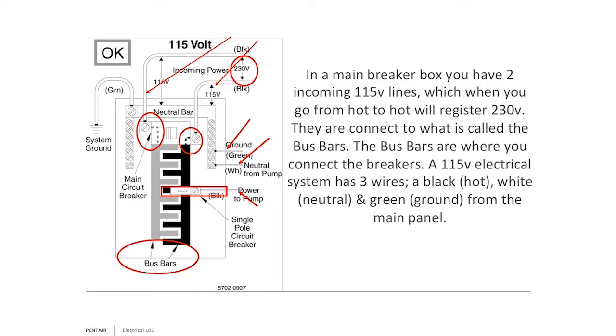A floating ground can cause stray voltage to stay on the ground. To test the ground, use a low-voltage detection pen — push the button and put it near voltage and it will sound indicating the circuit's live. But if in doubt, pull out your voltmeter, set it to voltage AC, and if you touch ground to anything metal — the screws on the circuit panel, bare conduit — you should not measure more than half a volt AC. If you do, get an electrician involved. Please don't get adventurous and get hurt.